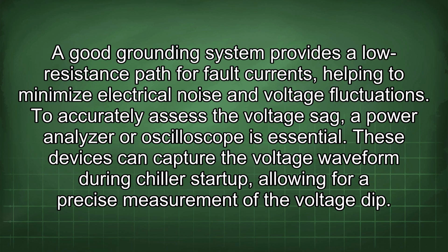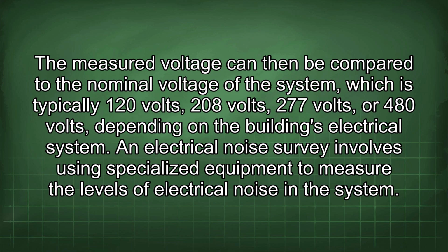To accurately assess the voltage sag, a power analyzer or oscilloscope is essential. These devices can capture the voltage waveform during chiller startup, allowing for a precise measurement of the voltage dip. The measured voltage can then be compared to the nominal voltage of the system, which is typically 120 volts, 208 volts, 277 volts, or 480 volts, depending on the building's electrical system.